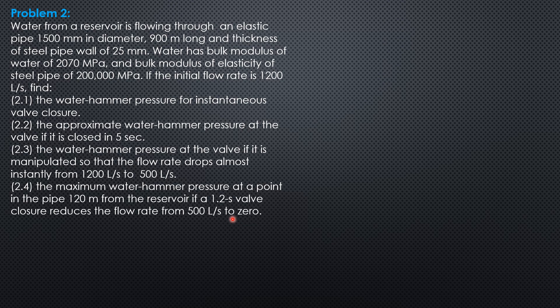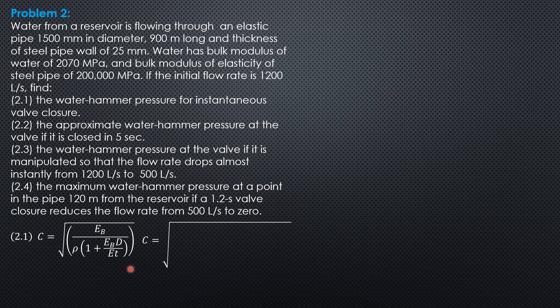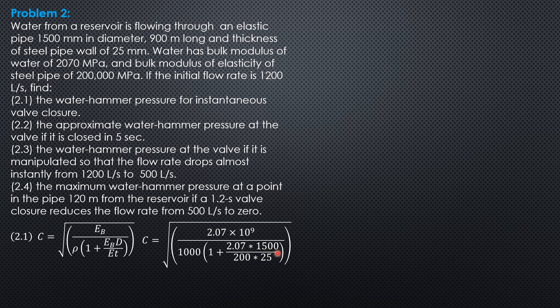First, compute the celerity, because for instantaneous valve closure, water hammer pressure is C times density times velocity divided by 1,000 to express it in kilopascals. C equals the square root of the bulk modulus of the fluid over density, times the quantity 1 plus bulk modulus of water times diameter over bulk modulus of pipe wall times wall thickness. Substituting: square root of 2.07 × 10⁹ Pa over 1,000 times (1 + 2.07 GPa × 1,500 mm / (200 GPa × 25 mm)). Celerity C = 1,030 meters per second.